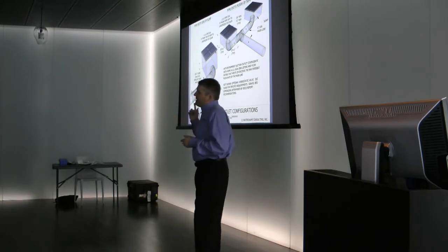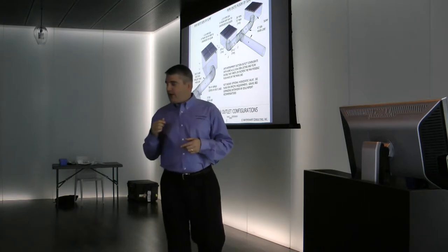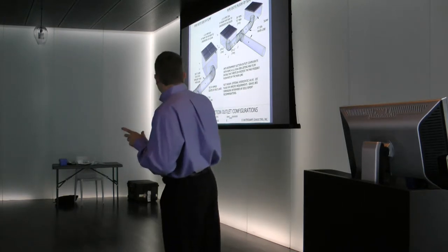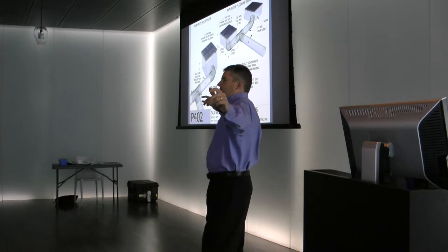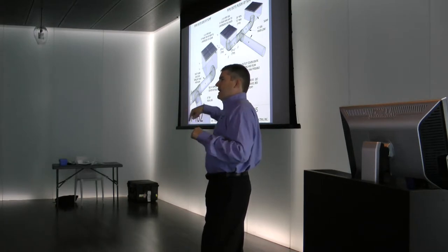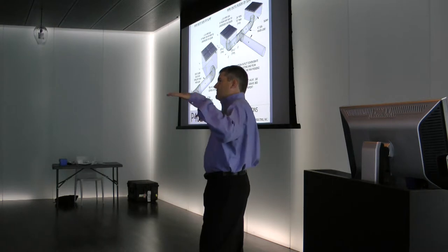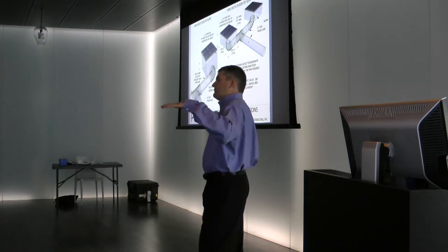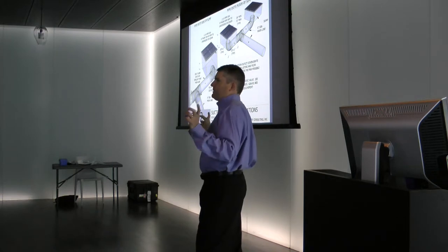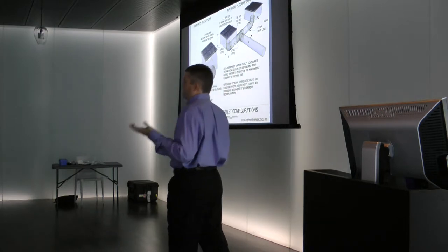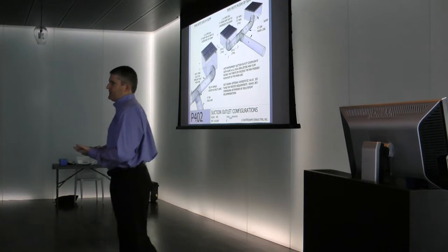The 72-inch max, actually, this is just in our detail. The reason that I have that in there is that if you put the drains really, really far apart, you'll have more head loss in the lines, more friction, and that will actually create a higher hold down force in the drain that's blocked. So having them too far apart can also be a problem because there's more head loss and that creates a pressure differential, which is your hold down force.